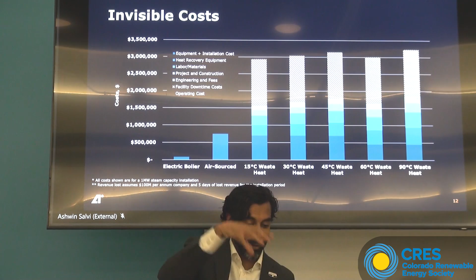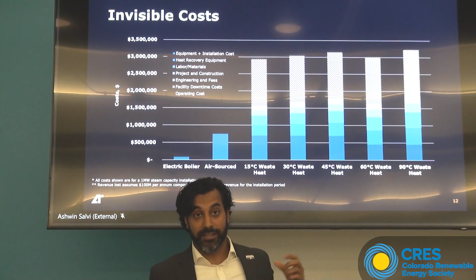The waste heat-driven systems, the biggest challenge is you have to do a lot of customization per facility to go get that waste heat. If you've got a facility here and the waste heat located over there, you now have to deploy hardware, which requires engineering, to go get that waste heat, store it, and then use it to drive a waste heat-driven heat pump. This ends up being expensive for the engineering effort, the hardware to deploy, and also the facility downtime. If you're trying to get waste heat from someplace, you've got to shut down the manufacturing to go get that waste heat. When you look at it, that ends up being roughly 3 to 6 times the capital cost of just the heat pump itself.